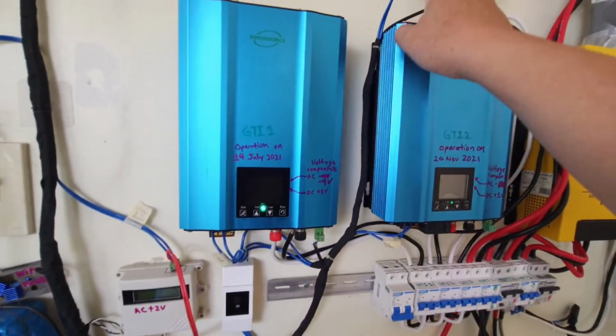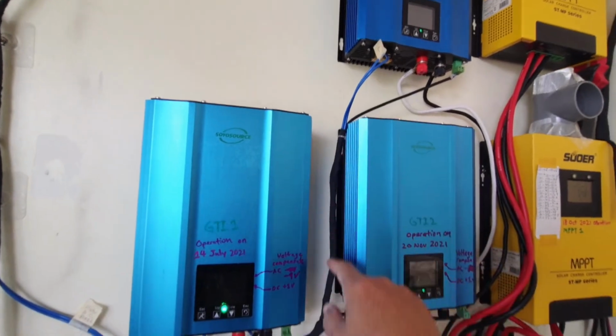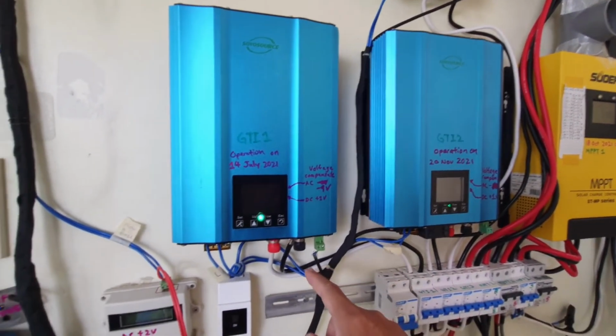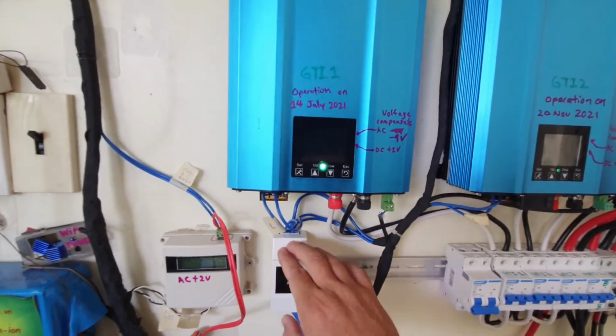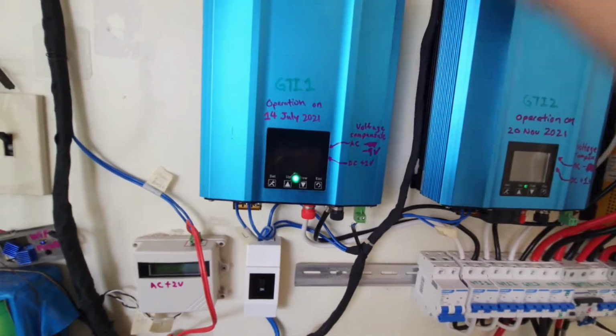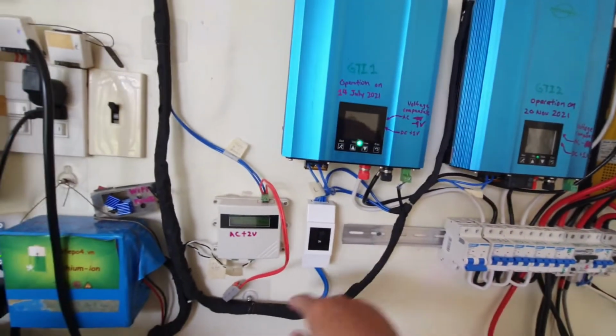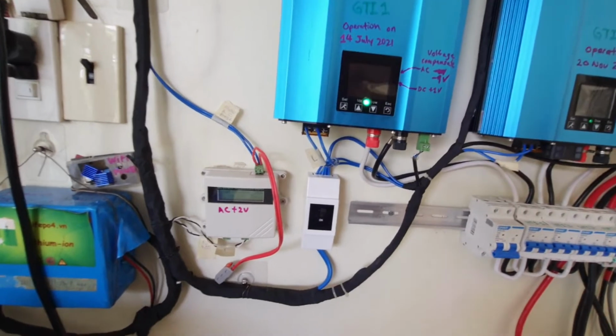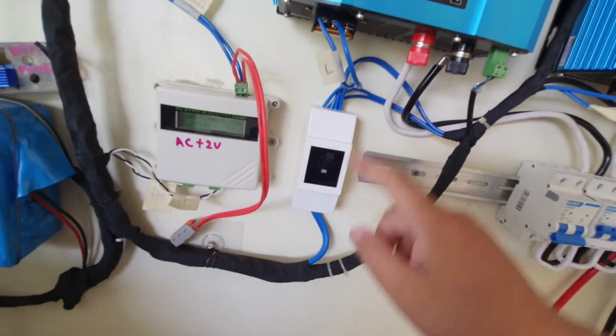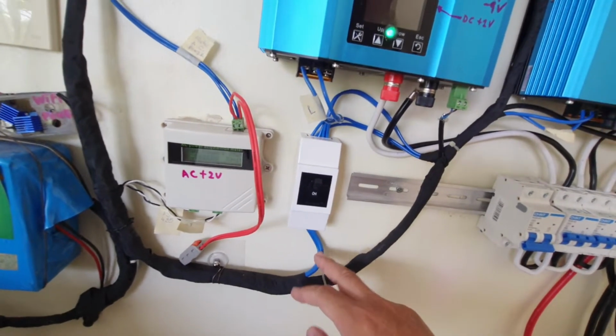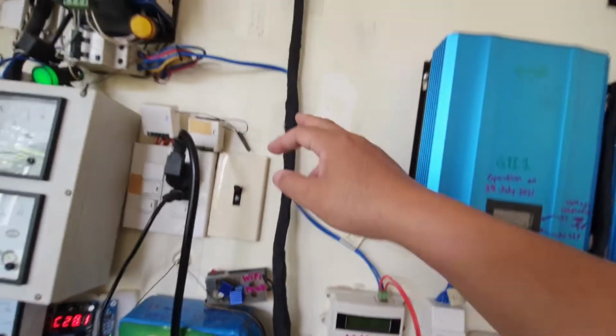So all the AC side cuts in here and goes into this switch, which also switches the grid tie inverters on and off. This blue color line, the thick one, is much thicker than the rest because it carries 2.7 kilowatts at max.